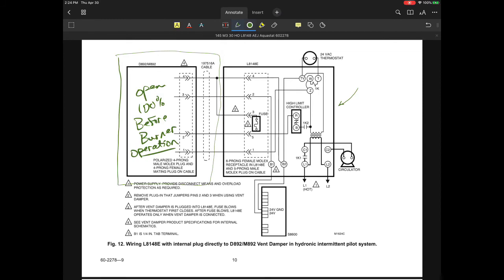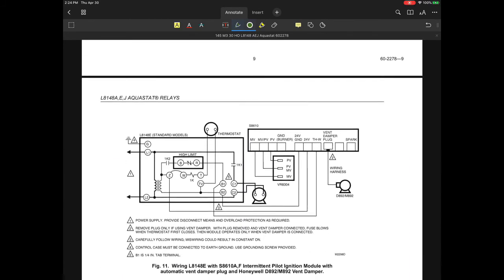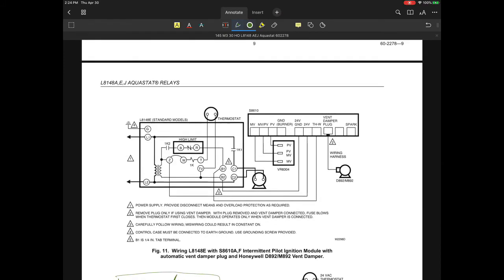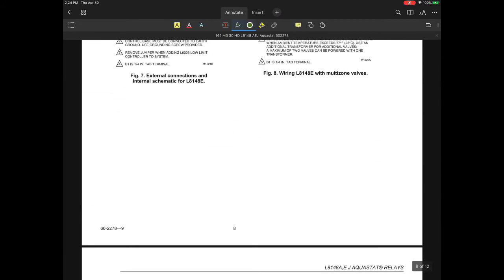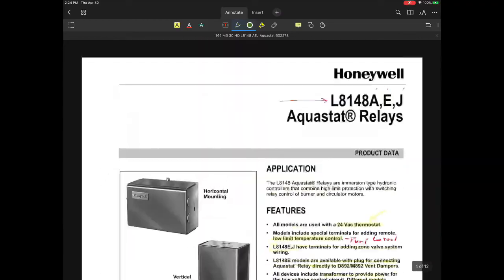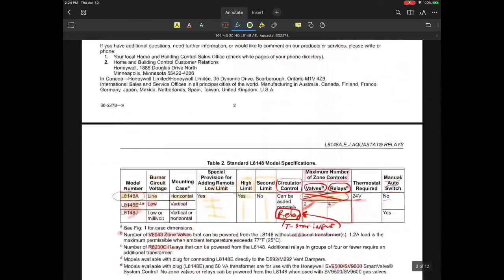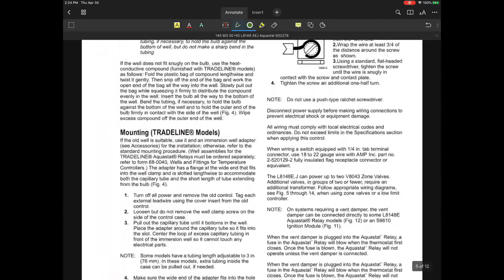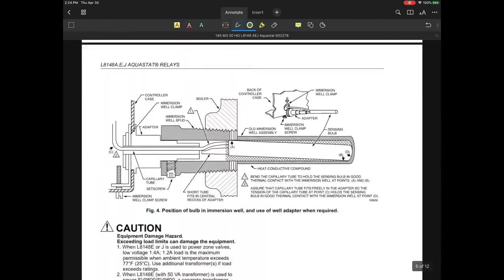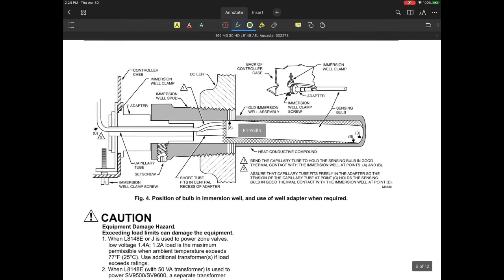Now, if you are natural draft, if you are using an induced draft type boiler, then you will not have a vent damper at all. And again, very similar, but the thing you have to recognize is you have to be able to isolate the problem. When you're diagnosing systems, you have to isolate parts and pieces. Is the Aquastat doing its job? Is the vent damper doing its job? Am I getting the correct inputs into the Aquastat? You have to look at those things to go through the diagnosis for that. All right. So that is a little bit on that.